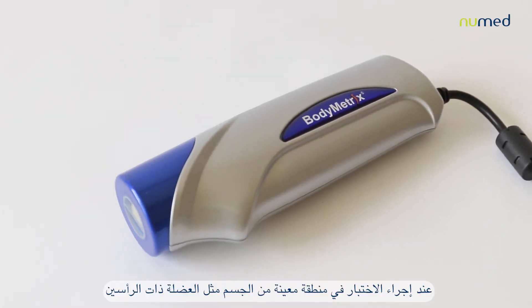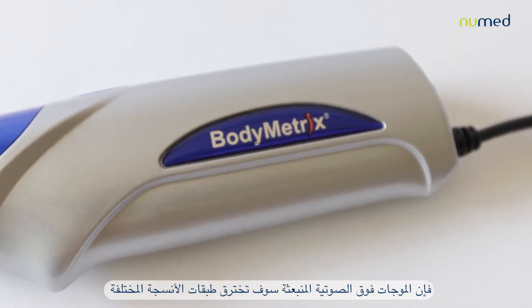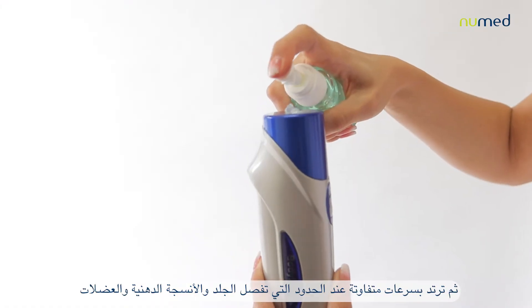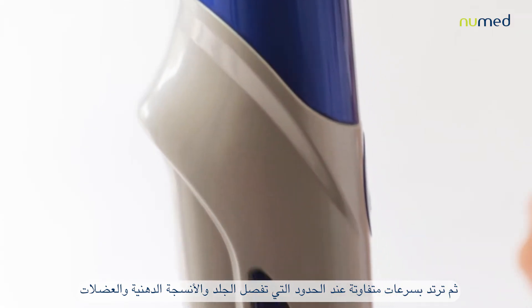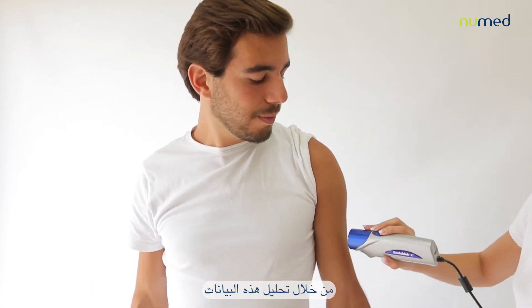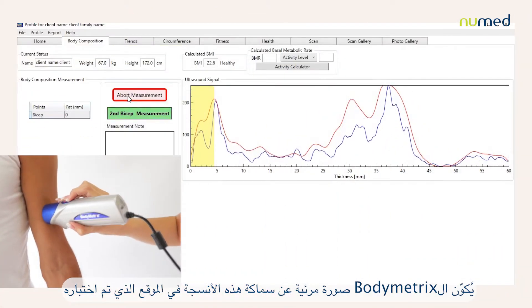At a specific body area — such as the biceps, thigh, chest, waist, and others — the ultrasound waves emitted will run through the different tissue layers and will be reflected at different speeds at the boundaries of the skin, fat tissue, and muscles. Through analyzing these data, the BodyMetrix will provide a visual display of the thickness of these tissues at the specific site tested.